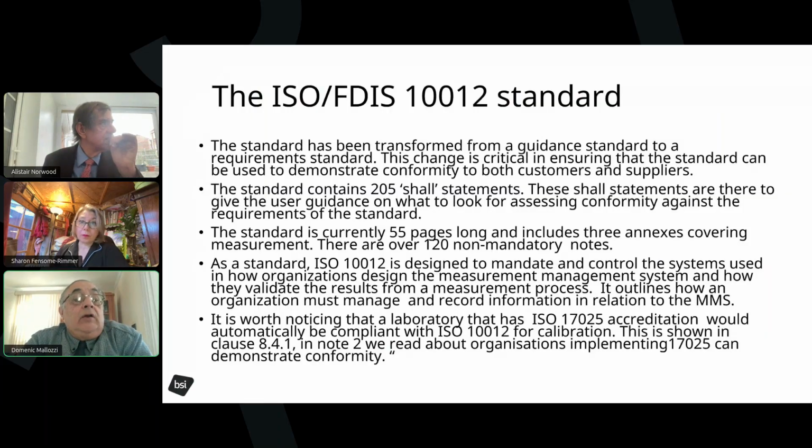The only time you have to worry about the calibration laboratory task is when you have a calibration lab inside of your organization. And we discussed that in, I think, clause 8 further. But for those of you who don't have an internal calibration lab or internal conformance testing, when a company provides you a 17025 certificate of calibration, a test, it has all the data you need to meet the requirements of 10,012 the way it's stated. And there is no need for them individually to be 10,012.